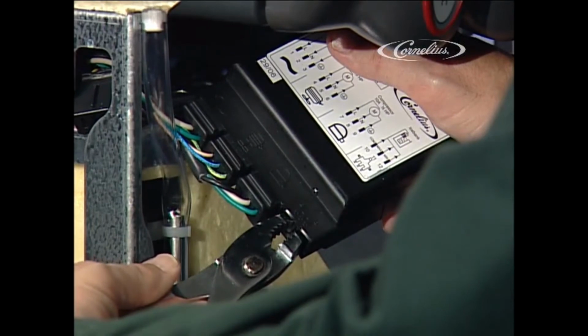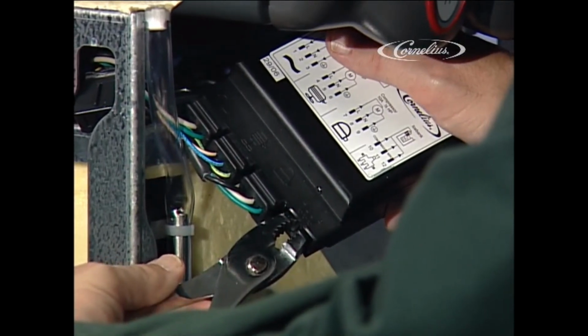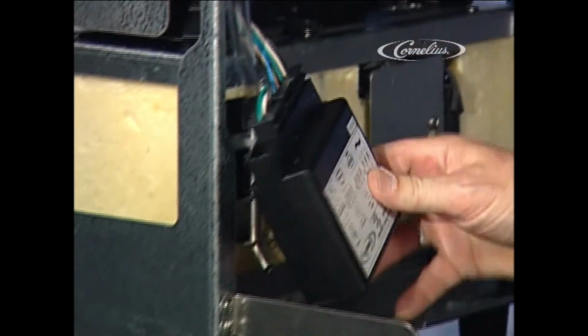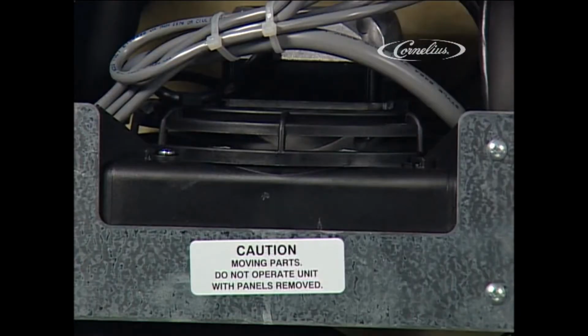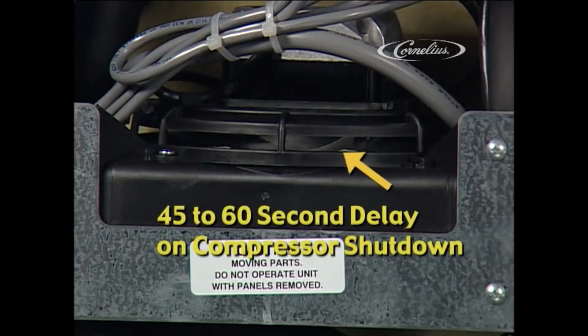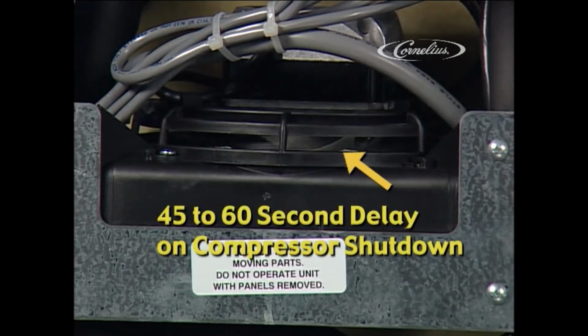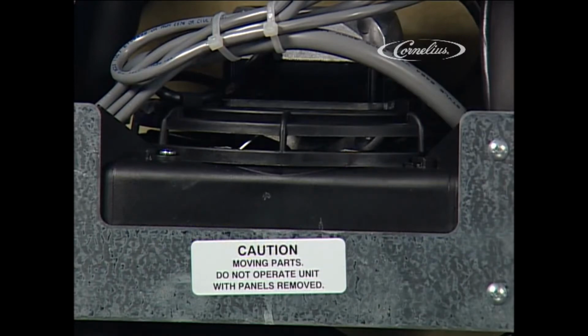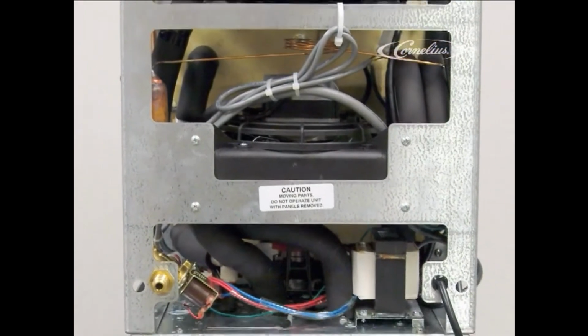After we have run the system for about a minute, let go of the pliers and you will get a 45 to 60 second delay and the compressor and condenser fan will shut off. What we have done with this test is validate that indeed the IBC operating circuit is sending the signal to the compressor and that the relay has engaged to send voltage to the condenser fan and compressor to activate the refrigeration system.